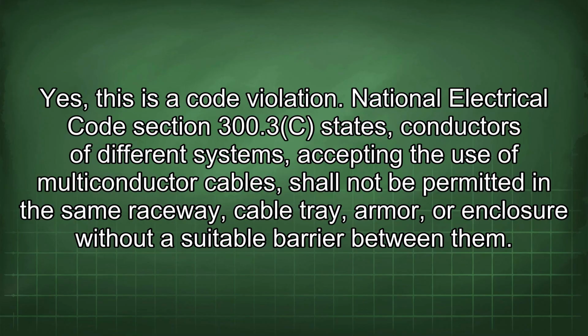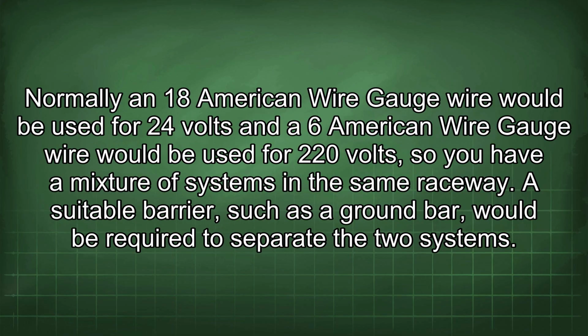Yes, this is a code violation. National Electrical Code Section 300.3(C) states conductors of different systems, excepting the use of multi-conductor cables, shall not be permitted in the same raceway, cable tray, armor, or enclosure without a suitable barrier between them. Normally an 18 American wire gauge wire would be used for 24 volts and a 6 American wire gauge wire would be used for 220 volts, so you have a mixture of systems in the same raceway. A suitable barrier, such as a ground bar, would be required to separate the two systems.